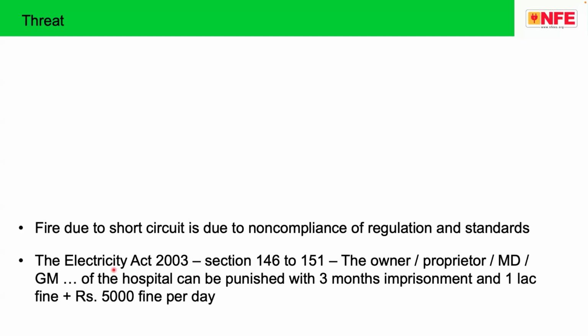We have the Electricity Act 2003. Sections 146 to 151 of the Electricity Act say, if you have an unsafe situation, what is an unsafe situation? Your MCBs are unable to trip. You are having, let us say, one hospital caught fire. The reason is short circuit. Why the short circuit? Because your installation is not in compliance with the standard. In such a case, the owner, the proprietor, the managing director or general manager of the company or the hospital can be punished with 3 months imprisonment and 1 lakh fine plus 5,000 rupees fine per day. There is a provision in the Electricity Act. So if there is an accident, of course, there is a challenge. Please be careful about this.